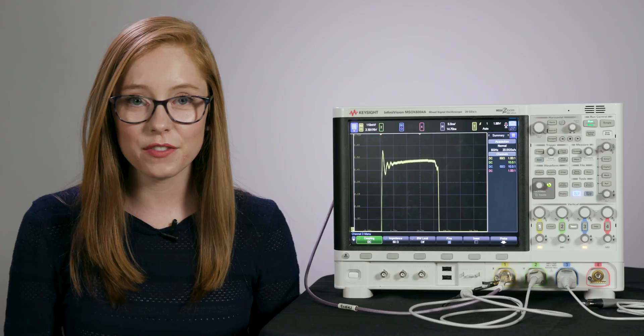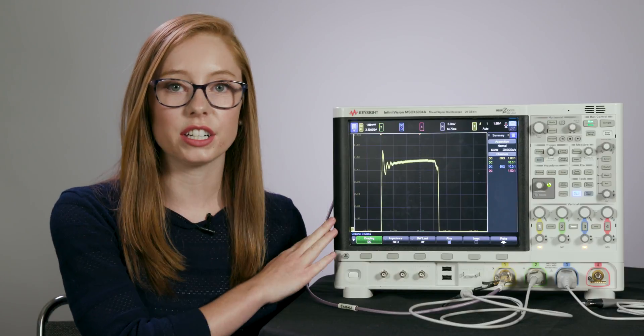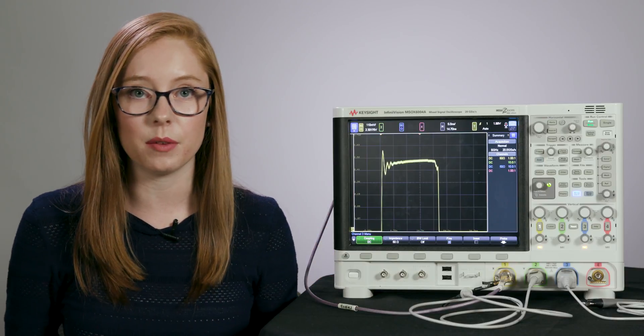To make things worse, the second effect of probe loading could come into play. The signal that you see on your screen could be far different from the signal as it exists on your device. Let's see what the signal looks like through the passive probe that we've been using.